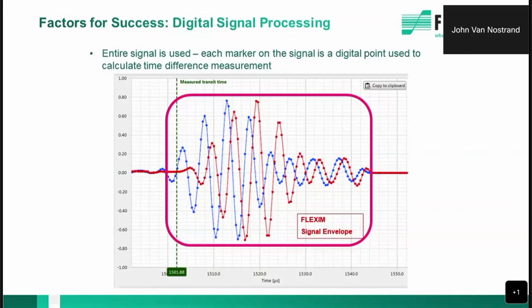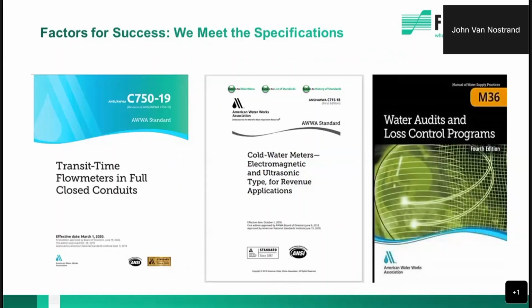So if you had, depending on the frequency of the transducer, it could be anywhere from 80 to 200 of these digital marks, and we're counting them all. So now not only do we have a detection for signal, meaning that if you send 100 pulses and you receive 50 of them, you have 50% signal strength. That's pretty easy. But we're doing the same thing, but we're also measuring the fidelity of the wave. So we have a quality measurement as well. So we can actually operate with low signal and have a very good quality signal. And an example, when would you see that? Maybe on sludge lines, ductile iron pipe with cement liner, or precast concrete pipe. We're able to do those applications where other competitors can't for this reason.